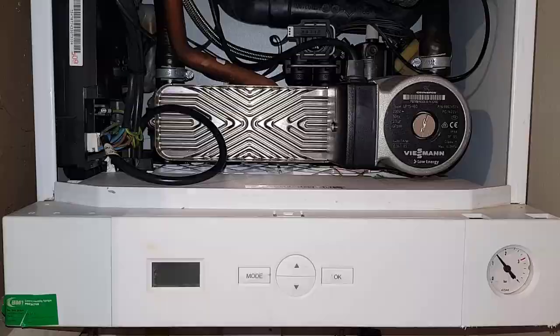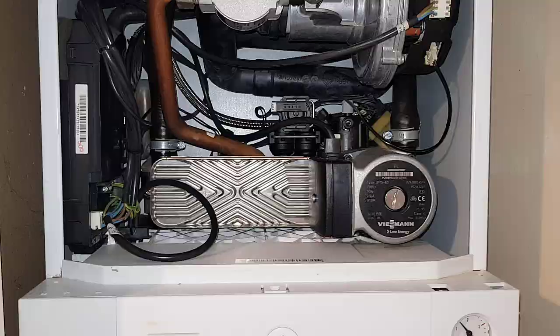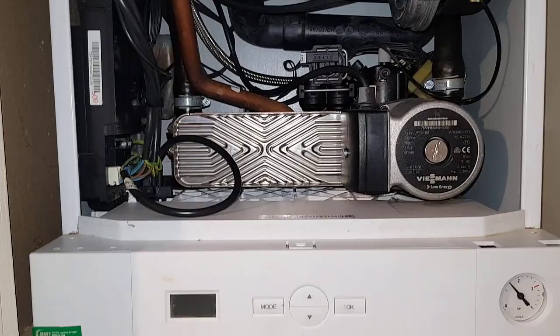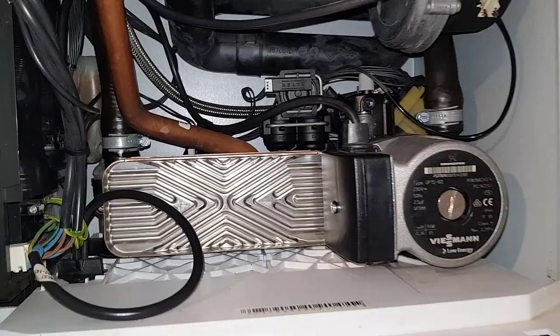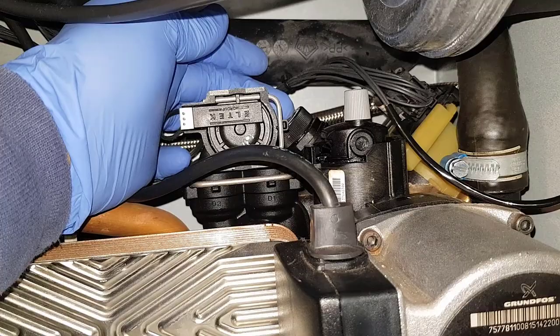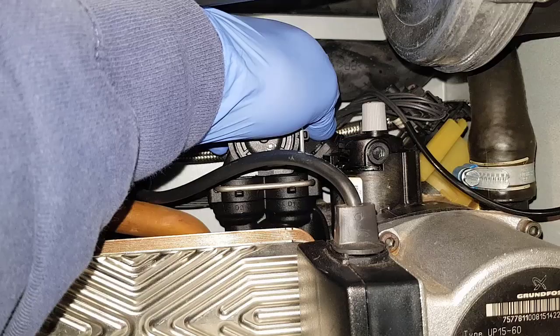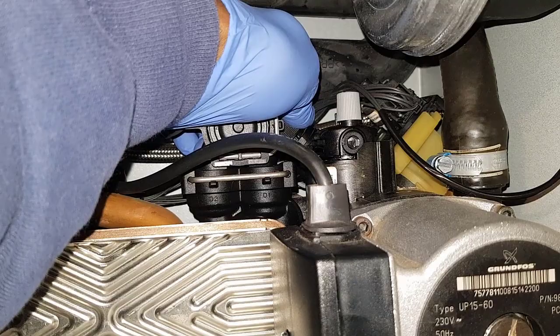Now on this boiler there's no drain point on this particular one — on these 50s, this is the base model of the Viessmanns, so there's not a good drain point. The only way I'm going to have to drain it is through the PRV, which a lot of people say no to, but it's happening. The PRV is kind of disguised where my finger is — it's all in black so you can't see it.